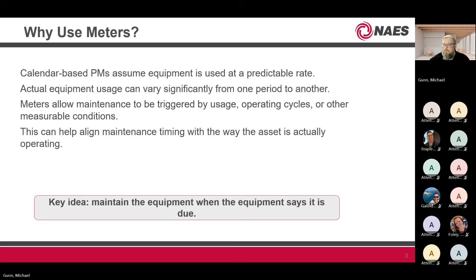Specifically, a meter is a record with a measurable value associated with an asset or location. It gives you a history of all these readings and conditions, ranging from run hours, starts, cycles, mileage, pressure, temperature — any kind of meter you have on the plant, we can basically duplicate in Maximo and track, similar to a logging software. Then we can use these meters as part of preventive maintenance scheduling and planning.